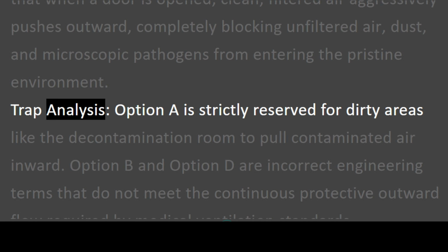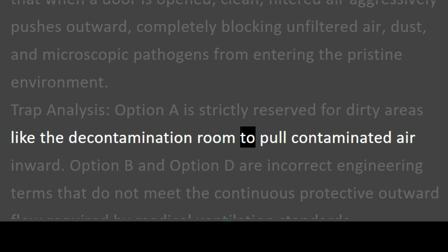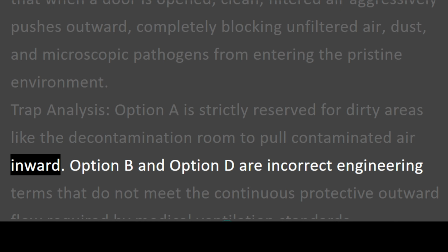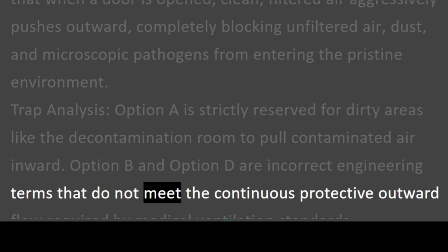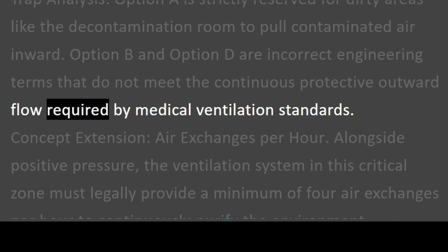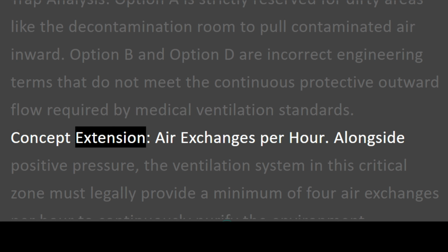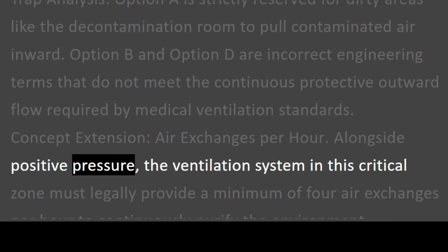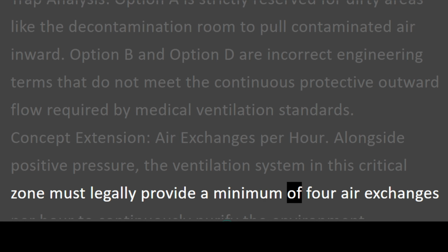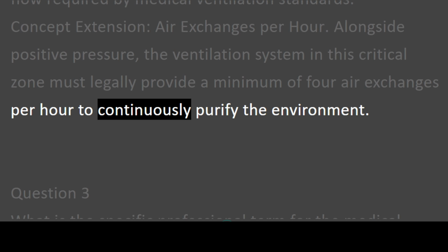Trap analysis. Option A is strictly reserved for dirty areas like the decontamination room to pull contaminated air inward. Option B and Option D are incorrect engineering terms that do not meet the continuous protective outward flow required by medical ventilation standards. Concept extension, air exchanges per hour. Alongside positive pressure, the ventilation system in this critical zone must legally provide a minimum of 4 air exchanges per hour to continuously purify the environment.